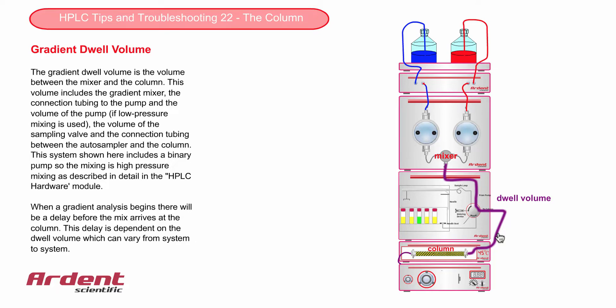This time is known as the delay time. This means that for the first 1 minute of the analysis, even if the gradient profile begins immediately, the column will still have the initial mobile phase mix and will be running in isocratic mode.